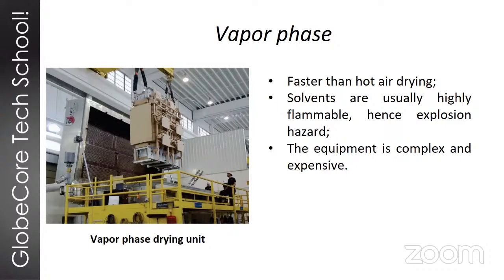So this method is good for all sizes of transformers, but once again, it's mostly usable if you have a repair shop with all this equipment. The biggest limitation is that those solvents are flammable, and there is a risk, obviously, that at a certain concentration of vapor and air, the mixture becomes explosive. So this equipment can be quite expensive because it needs to be intrinsically safe. So there is a certain risk associated with this process and certain costs. All right, next slide, please.